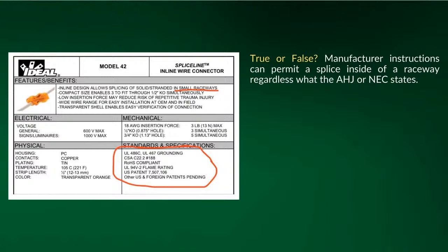So what happened was the gentleman said the general contractor cut a line - I don't know exactly what it was, probably a branch circuit that fed out to an outbuilding. They tried to pull the wire out, but it was stuck, wouldn't move. So they decided to use this Ideal inline splice and splice it for like 12 to 14 inches to the other J-box, then re-splice it there.